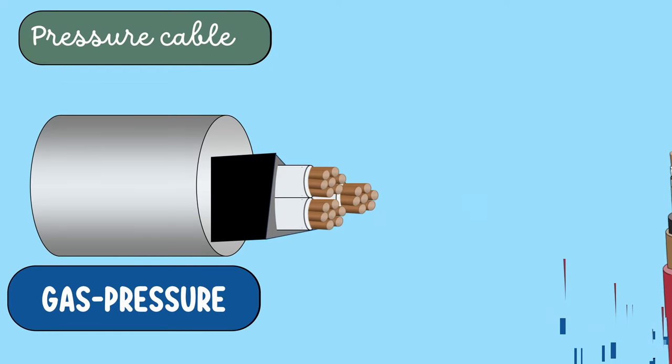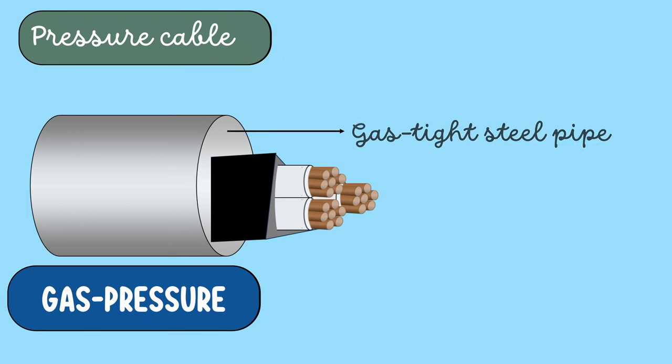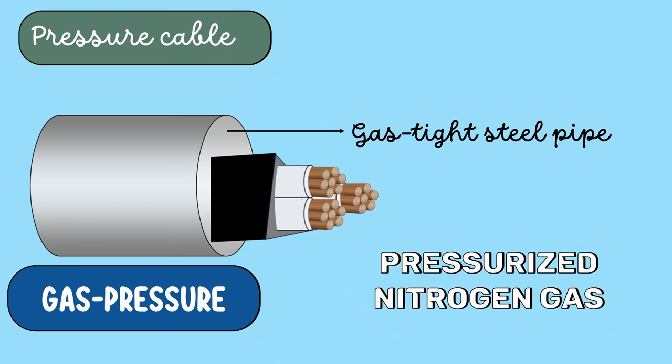Now, let's talk about gas pressure cables. Here, the cable is very similar to solid type cable except that it is of triangular shape. The cable is placed inside a gas-tight steel pipe. The pipe is filled with pressurized nitrogen gas. The pressure closes the voids by compression. These cables can carry more load current and operate at higher voltages than a normal cable.